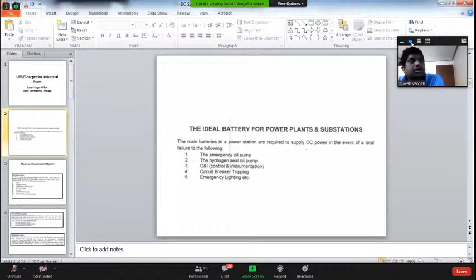So you can say there are continuous loads, momentary loads, and non-continuous loads. In an industrial plant, continuous loads include indication lamps and communication systems like PAGA systems, which are very important, and emergency systems. Some emergency lights and continuously energized coils need a continuous tripping supply, because when you lose supply, the breaker will trip. So you need continuous power supply to that coil.